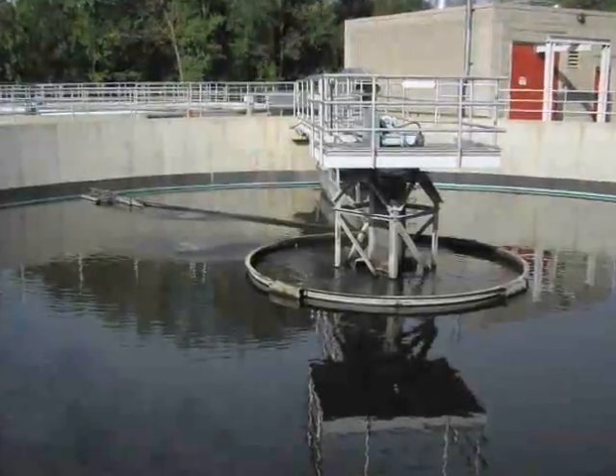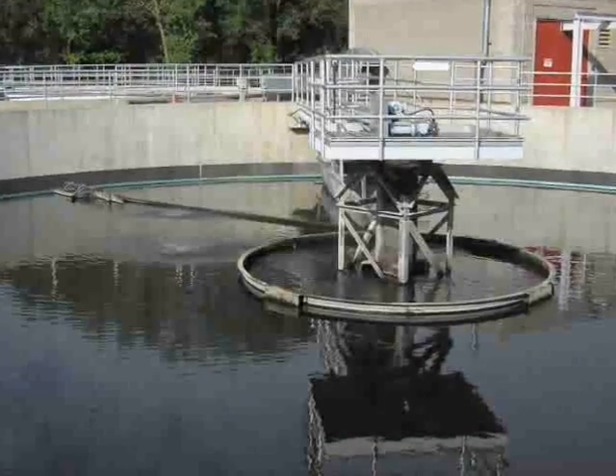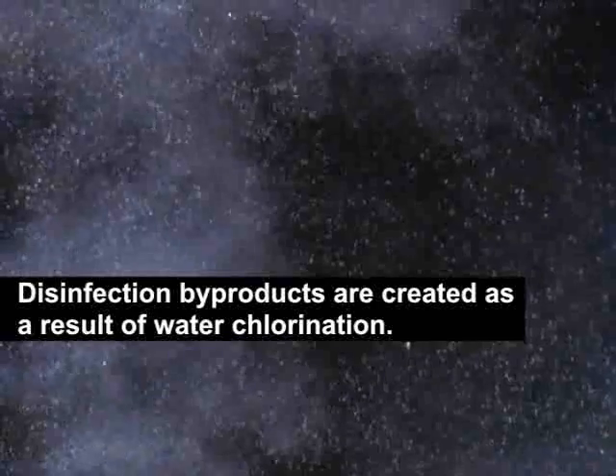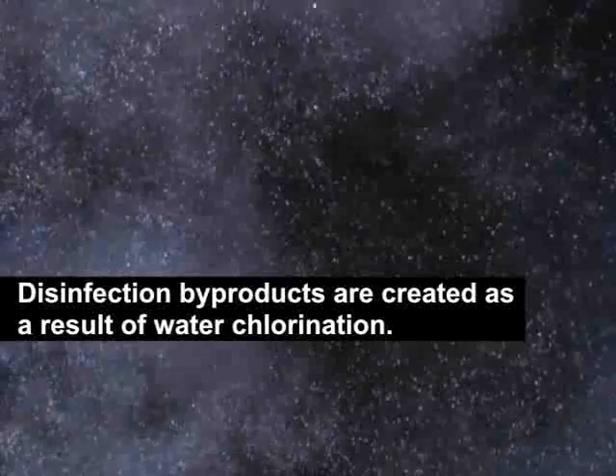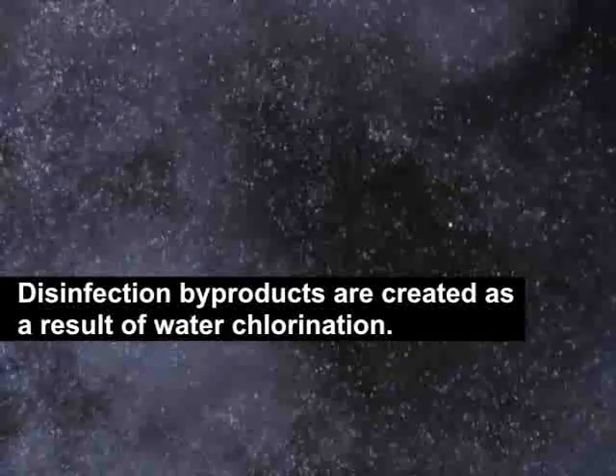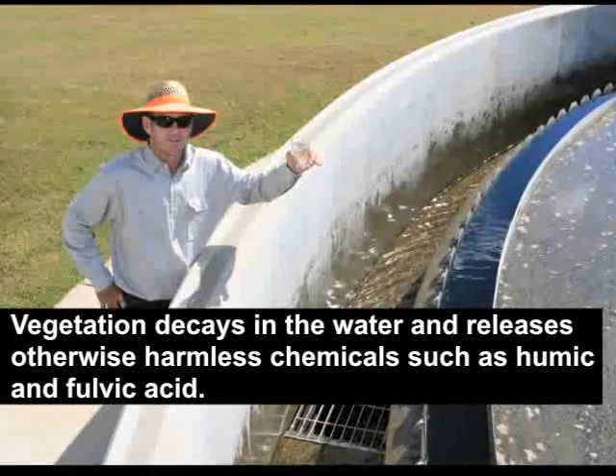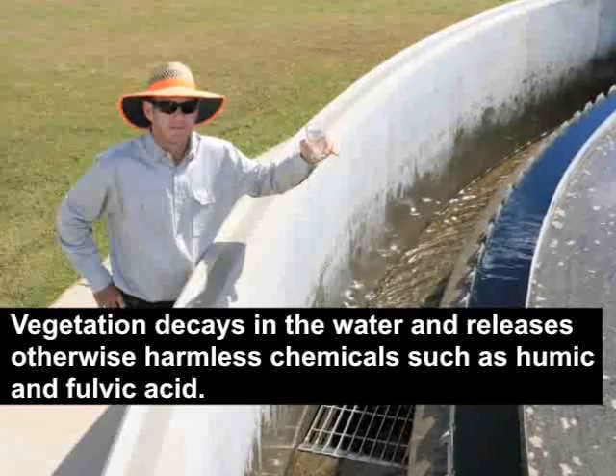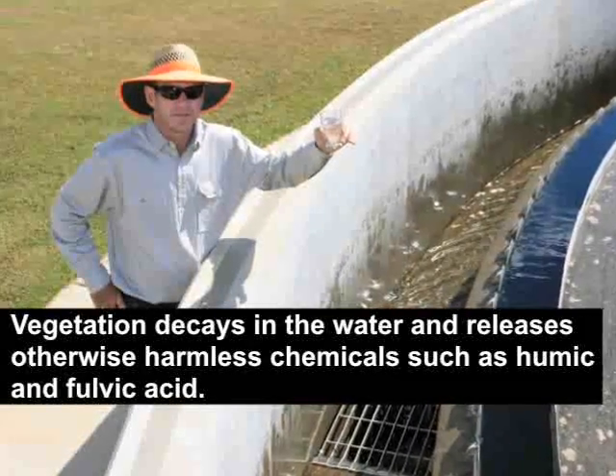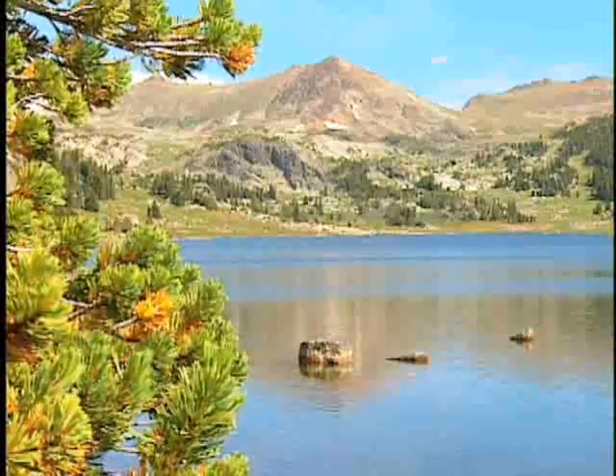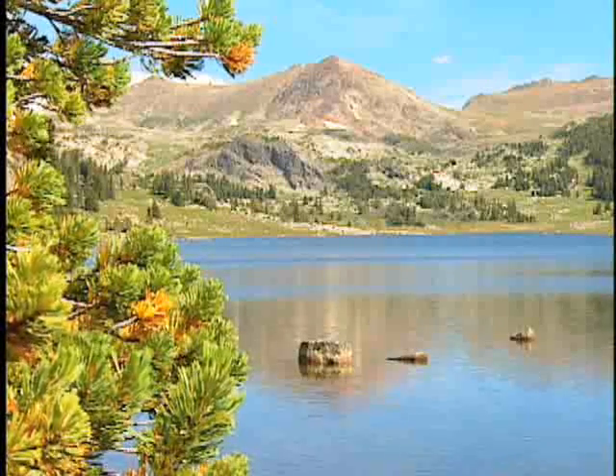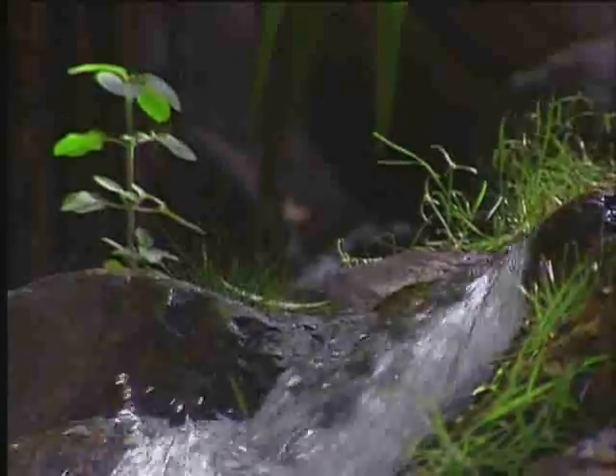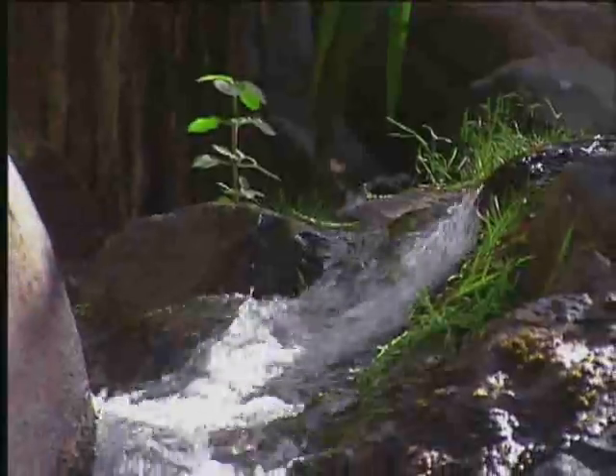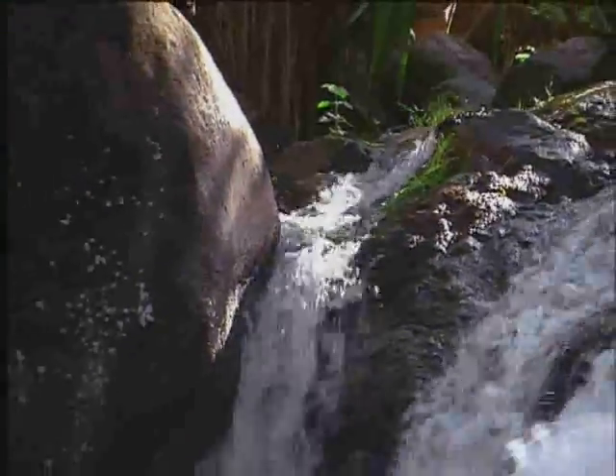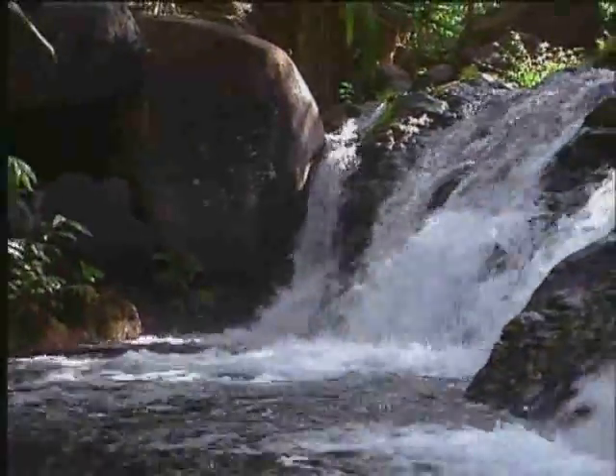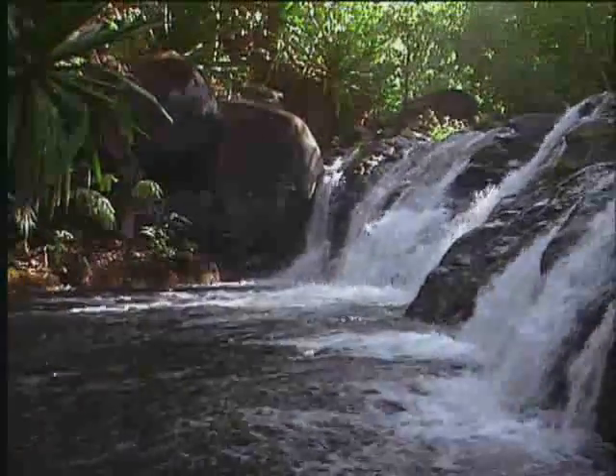These disinfection byproducts are a very descriptive term, because they exist as a result of disinfecting the water with the most common chemicals, typically chlorine. What they didn't realize for nearly a century was that these disinfectants, such as chlorine, chemically react with natural organic matter in the water. This natural organic matter typically comes from vegetation: the water has passed through the ground and is flowing in a stream, and leaves and grass fall in it and decay, releasing otherwise harmless chemicals known as humic and fulvic acid, which are sometimes even used in the health field.